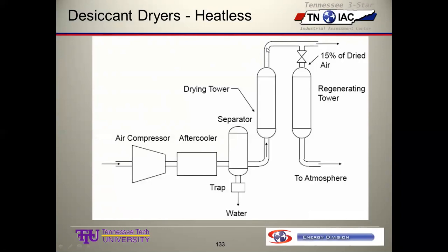So this is all of our compressed airflow. And we get over here, and we have a valve that opens, and 15% of the rated CFM on this dryer gets tapped off here and bled through the second tower to regen it. So this stuff, we've paid all this money to operate this thing to generate it. We dry it here, it's ready to go out to the system, and then we take 15% and we put it through here.